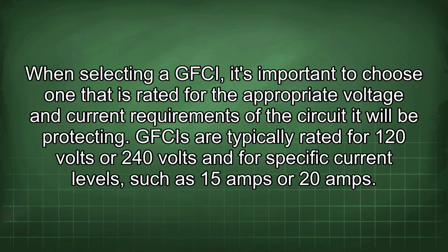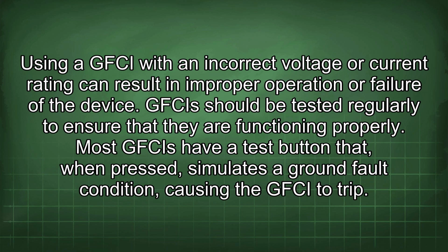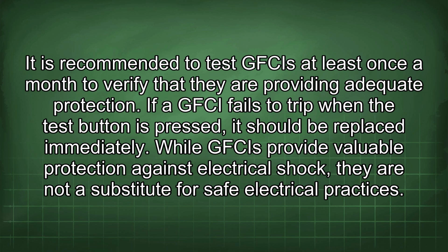GFCIs are typically rated for 120 volts or 240 volts and for specific current levels, such as 15 amps or 20 amps. Using a GFCI with an incorrect voltage or current rating can result in improper operation or failure of the device. GFCIs should be tested regularly to ensure that they are functioning properly. Most GFCIs have a test button that, when pressed, simulates a ground fault condition, causing the GFCI to trip. It is recommended to test GFCIs at least once a month to verify that they are providing adequate protection. If a GFCI fails to trip when the test button is pressed, it should be replaced immediately. While GFCIs provide valuable protection against electrical shock, they are not a substitute for safe electrical practices.